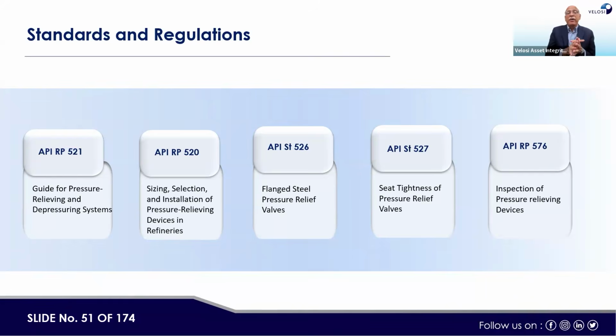And API STD 526. This one is basically a specification for purchase of the new PSVs. Whereas API STD 527 is about seat tightness of the pressure relief valve, how it should be managed. Whereas API RP 576 is generally for the operation phase, inspection and maintenance of the pressure relief devices. So these are basically the 5 standards.